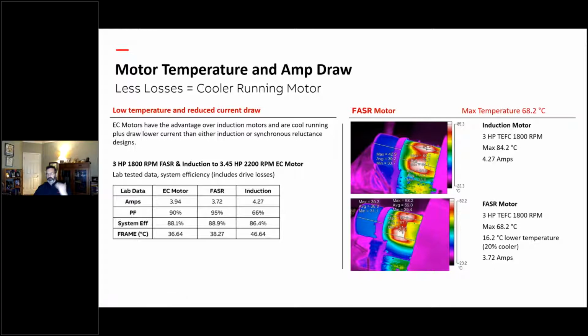It depends on where the cutoff is, but you may have had a 10 horsepower induction motor, and you might have to put a bigger drive on this induction motor than you would on this FASR motor design, because it's drawing less amps. And then this just shows an electrically commutated motor.